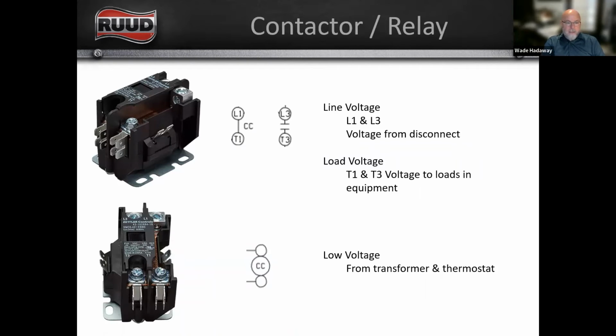So, contactors and/or relays. As I pointed out, and we all know this, the contactor or a relay typically has two different voltages, right? You've got a control side, and then you've got a line voltage side or a low voltage side. Up on the top, we're looking at our contacts. This is just like we have in the drawing. This is a single pole contactor, meaning that on the L1 to T1 side, there's just a copper bar there. And then we open that switch by opening L3 to T3, and that interrupts our flow of electrons. The way that we do that is we energize the coil, 24 volts to our contactor coil, which is depicted there in the drawing at the bottom.